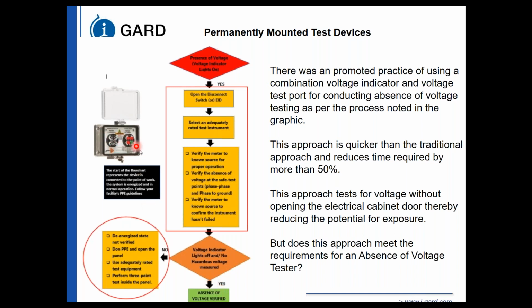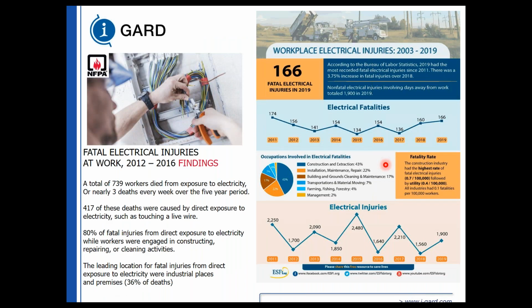All we've really done is establish that this device does not have voltage on it. There are still wires connecting this device to the back, and it reduces the time it takes to test for absence of voltage by 50%. However, we've shown that it cannot be relied upon because we're still finding a lot of people getting hurt and a lot of people are dying because of traditional practices that we have been using in the past. These numbers have not changed. 2018 is when NFPA 70E 2018 came out, and we're still not helping people go home at night.